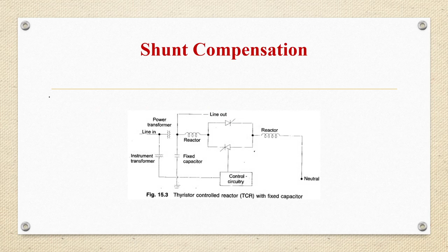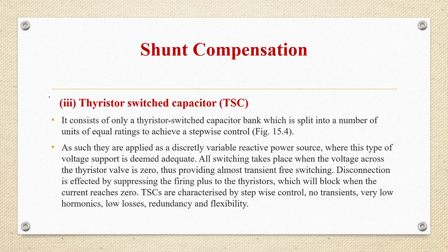The third one is the thyristor switched capacitor, TSC. It consists of only a thyristor switched capacitor bank which is split into a number of units of equal ratings to achieve stepwise control. As such, they are applied as a discretely variable reactive power source where this type of voltage support is deemed adequate. All switching takes place when the voltage across the thyristor valve is zero, providing almost transient-free switching. Disconnection is effected by suppressing the firing pulses to the thyristors, which will block when the current reaches zero. TSCs are characterized by stepwise control, no transients, very low harmonics, low losses, redundancy and flexibility.